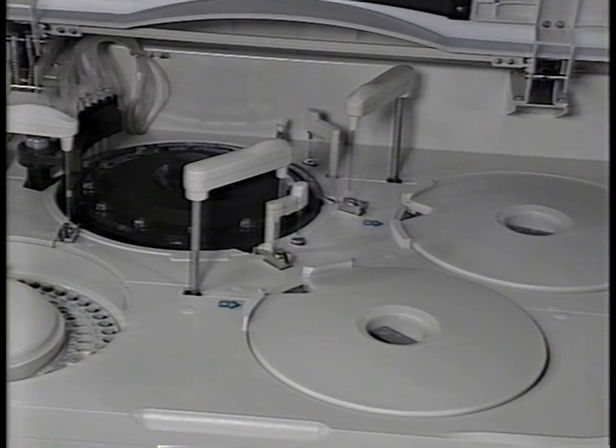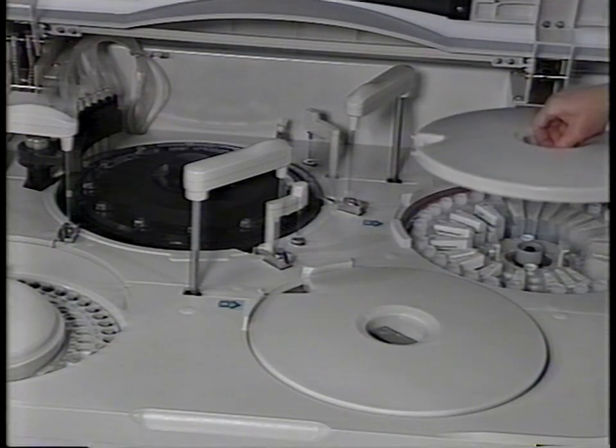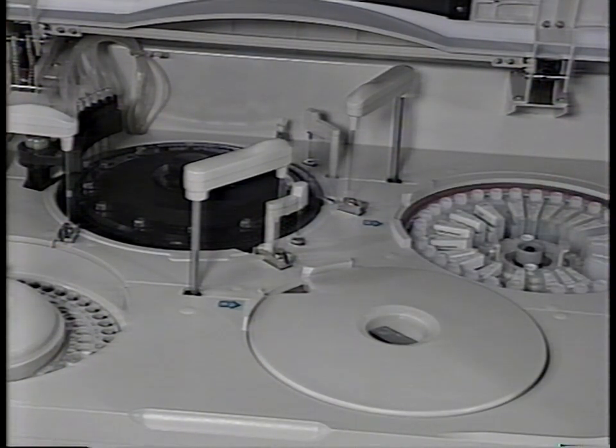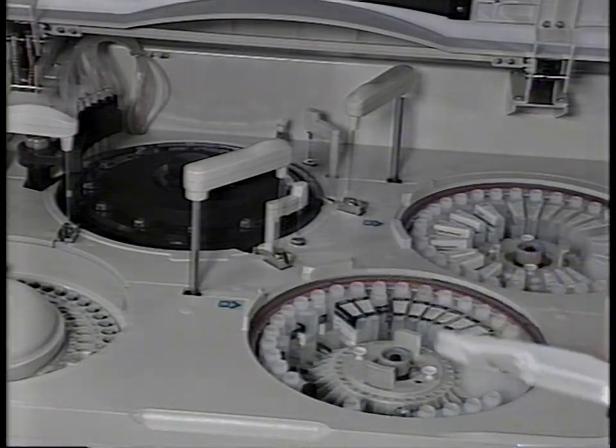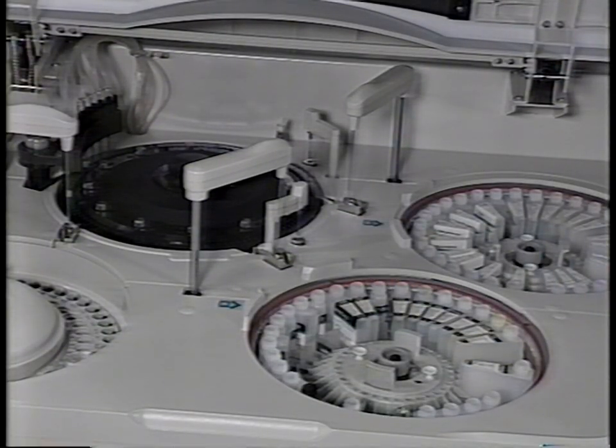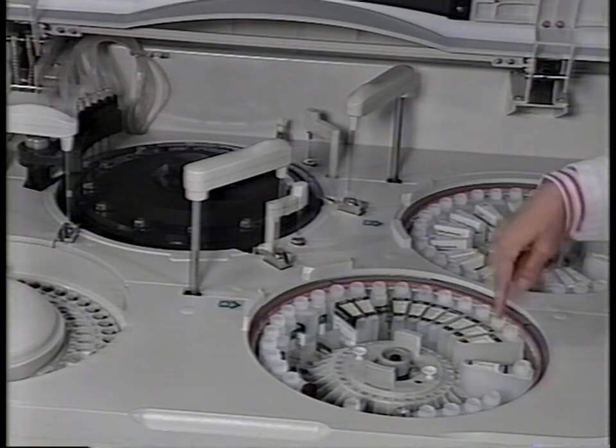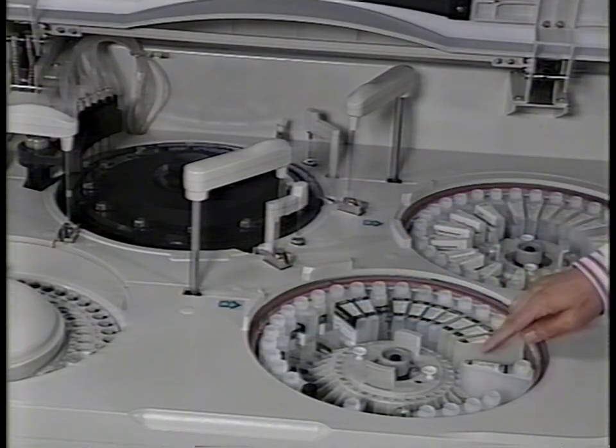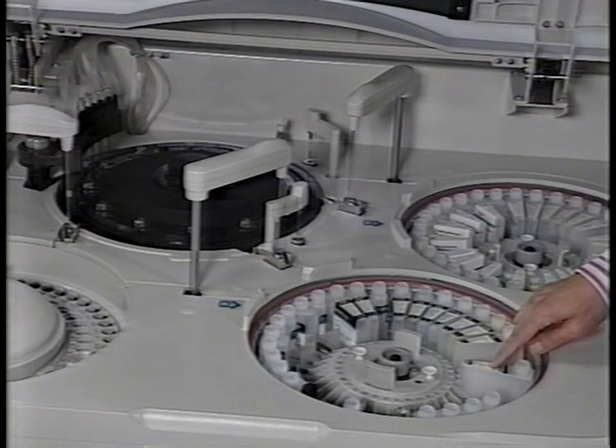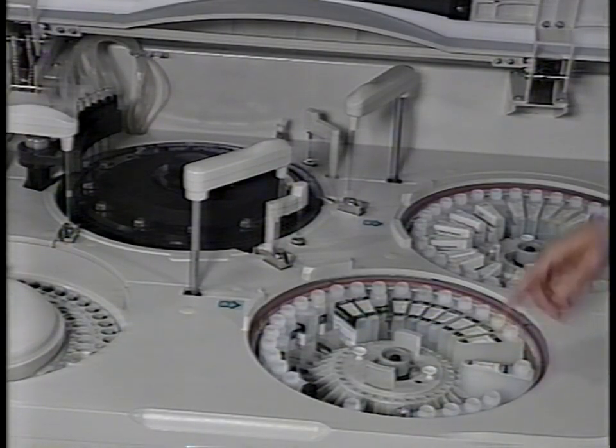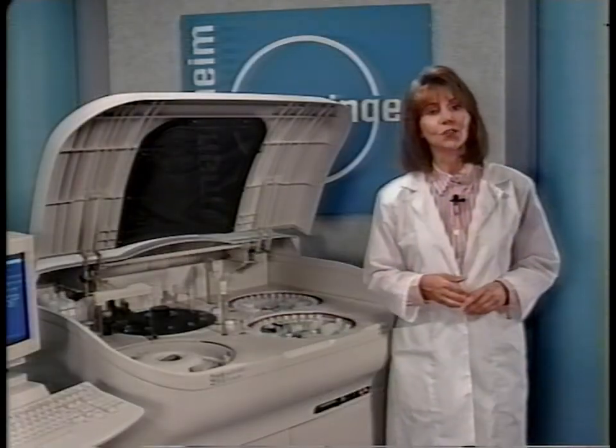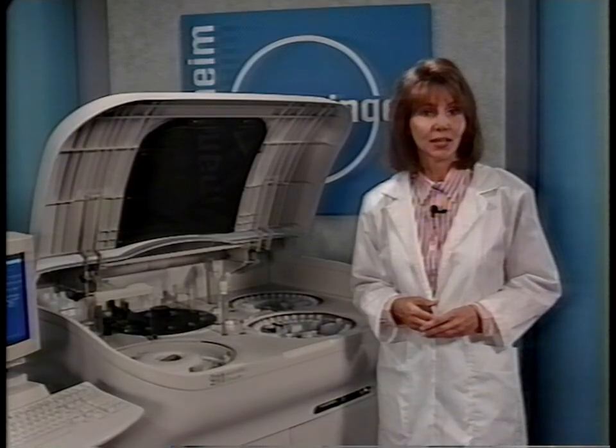Photometric reagents are stored in 2 reagent disks, one for white-labeled reagent bottles and one for black-labeled reagent bottles. The 2 reagent disks are identical, each with 33 positions. Position 33 is used for a detergent called Hydrogent. Therefore, there are positions for 32 reagents on each disc.